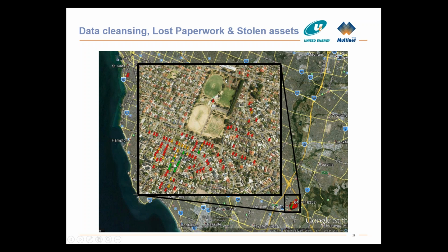Now, using the voltage profiles, we can pinpoint exactly where that meter is installed to the closest 50 meters. So we can confirm it's not installed at the coast, it is actually installed elsewhere, and we can pinpoint the property where it's installed, so we can send a field crew out and actually get the information from the meter.